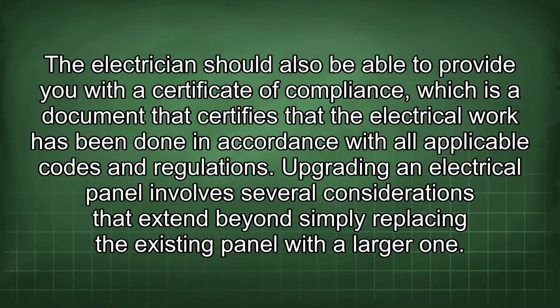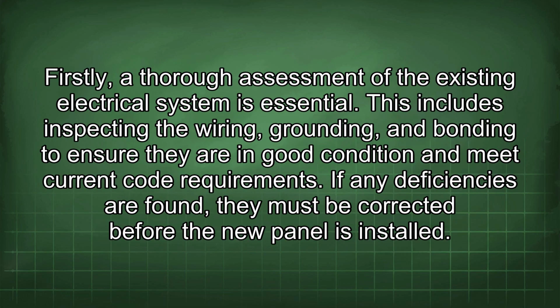Upgrading an electrical panel involves several considerations that extend beyond simply replacing the existing panel with a larger one. Firstly, a thorough assessment of the existing electrical system is essential. This includes inspecting the wiring, grounding, and bonding to ensure they are in good condition and meet current code requirements. If any deficiencies are found, they must be corrected before the new panel is installed.